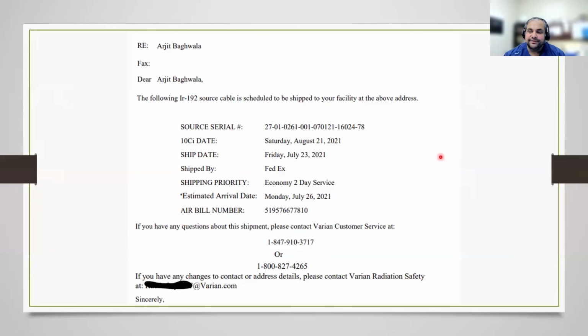So prior to the source being delivered, you will receive a letter that talks about the delivery information from the manufacturer. The document will have the source serial number, the shipping date, and the expected arrival date. And in our case, we also get to know the expected date when the source will be at 10 curies, the nominal activity. An advice will be to reach out to your machine engineer around the time you expect to do a source exchange, because often there are chances where this letter may not reach your inbox for some reason, and you do not want the source to be delivered at a different department within your hospital without you being aware.